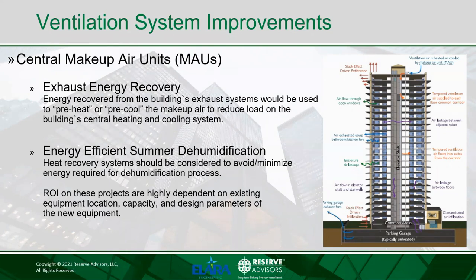I think back in the 60s and 70s, dehumidification was not considered to be a critical feature for building ventilation systems. So when summer dehumidification is considered, heat recovery systems can be utilized to avoid or minimize additional energy required for the dehumidification process, because there's a difference between a regular cooling process and a dehumidification process, and dehumidification requires significantly more energy. And this type of upgrade should be considered when the existing makeup air unit is scheduled for replacement as well, just to make it cost effective.